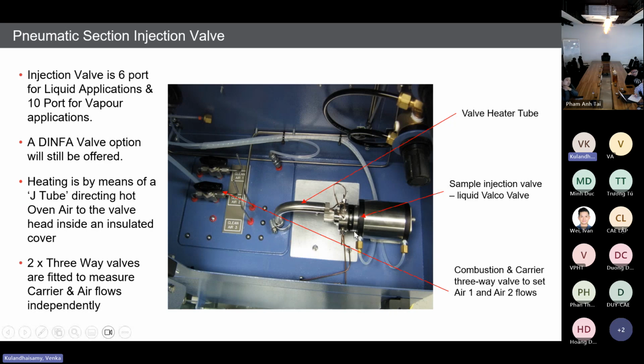Yes, here is a Valco injection valve. This is the rotary type valve. I told you already we have a linear type valve which is called the DINFA valve. So based on the application, our factory will choose either Valco or Infra. The injection valve is injecting 1 microliter of sample to the mixing chamber.